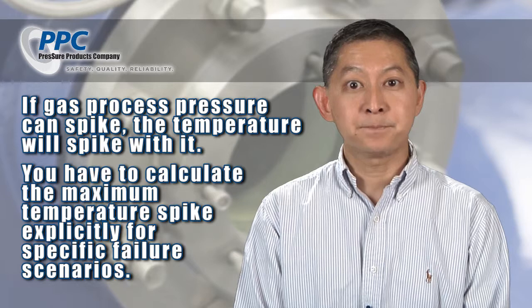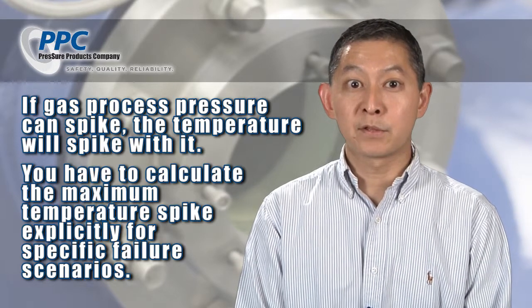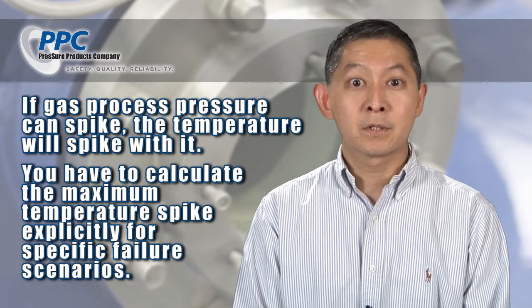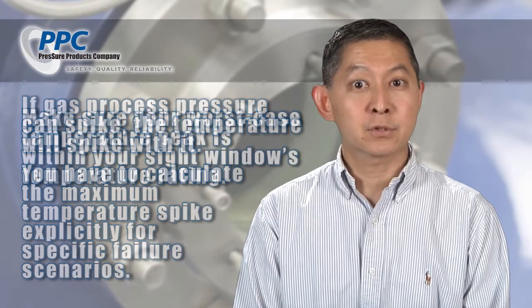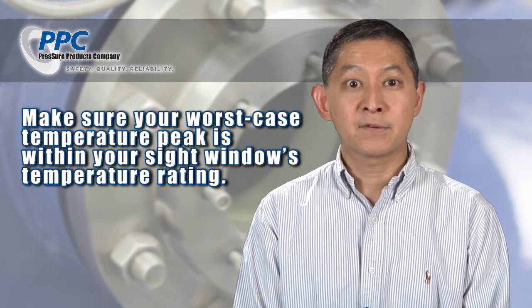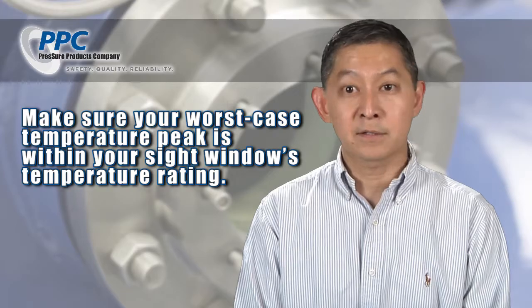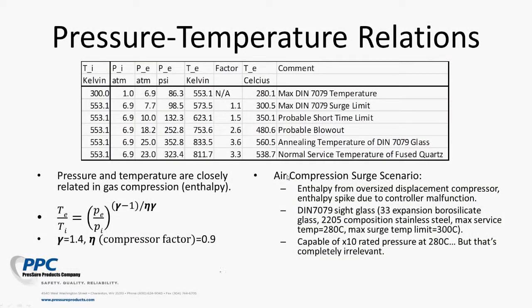And as I said already, sight windows are specified with no safety margins on temperature. So you have to explicitly account for the temperature changes and make sure to specify a unit that can accommodate the corresponding temperature rise. Let me give an example. For whatever reason, you decided that a pressure spike is possible, and you want to specify a sight window with a margin of safety on the pressure scale.